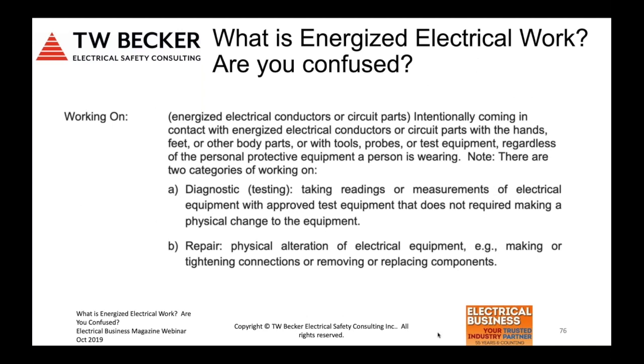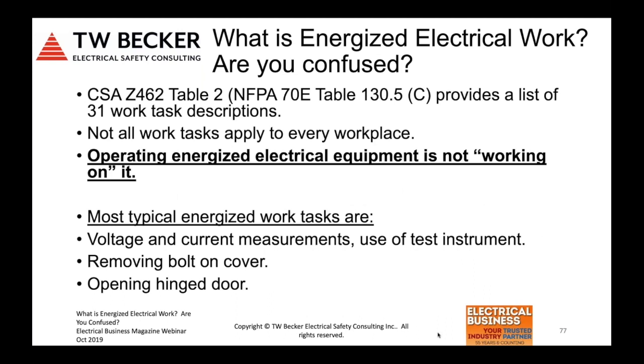What is energized electrical work? Are you confused? So I wanted to have the history, sort of the status quo, then have some slides here that really just very quickly cover: what is energized electrical work? The definition in Z462 and 70E is working on is diagnostics or repair. Those are the two high-level definitions of what working on is, but it's work task specific as identified in Z462 and 70E. They were always work task-based standards, but now we have the tables that have a discrete list of work tasks, and not all those work tasks may apply to every workplace. Operating energized electrical equipment is not working on it.